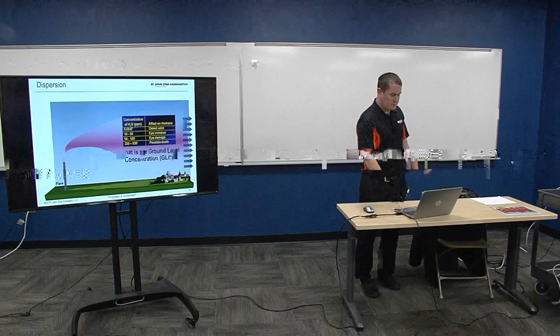like H2S, right? So if H2S got released from the flare, you'd want to know how it's going to be reacting with anybody or affecting anybody downstream. So dispersion is an important part of the design of a flare system, because you need to know if it's light or heavy gases. That's a big thing. The heavier the gas, the quicker it comes down and the more it stays together. There's lots of effects with dispersion also. So there's several ways to look at it.